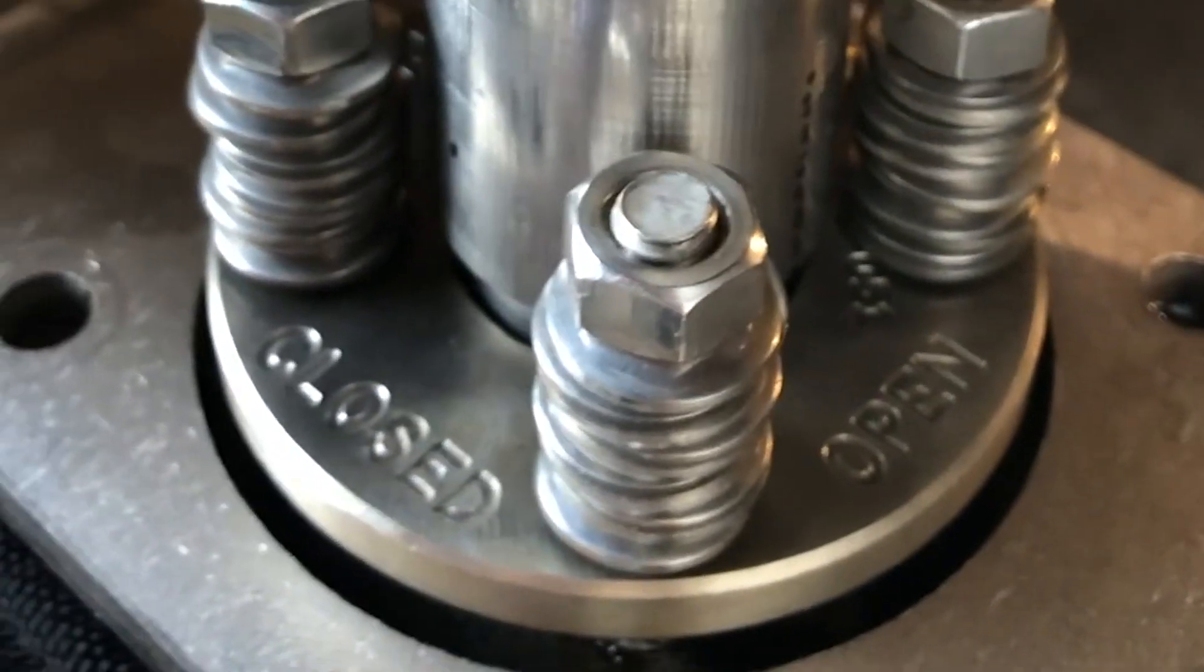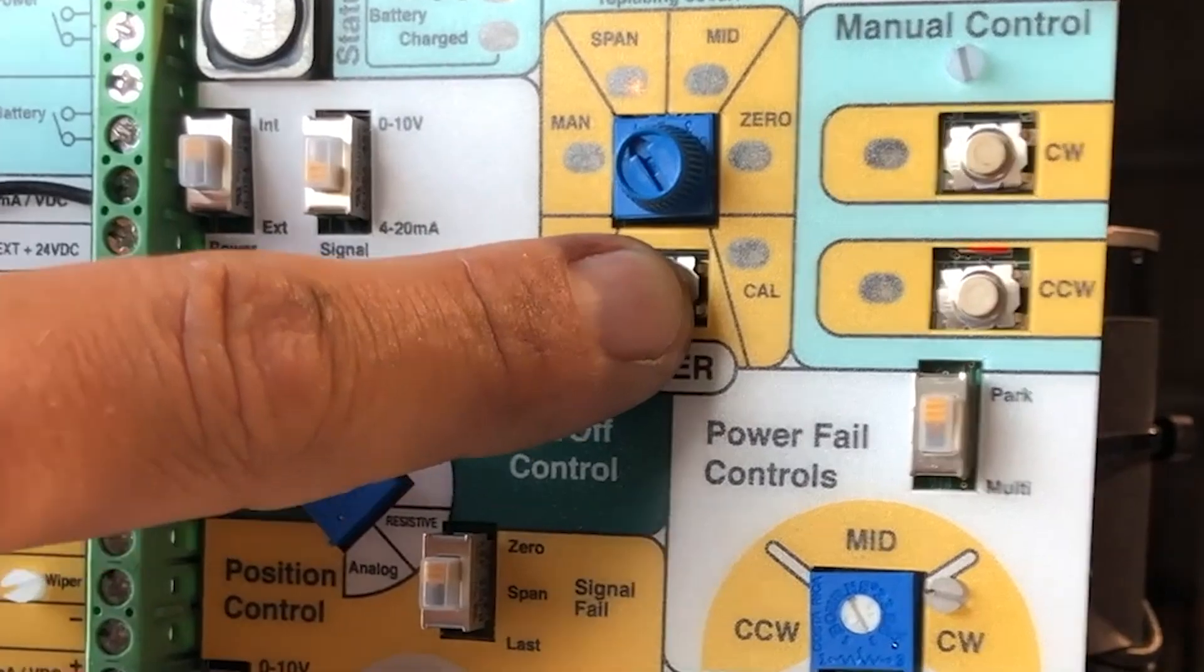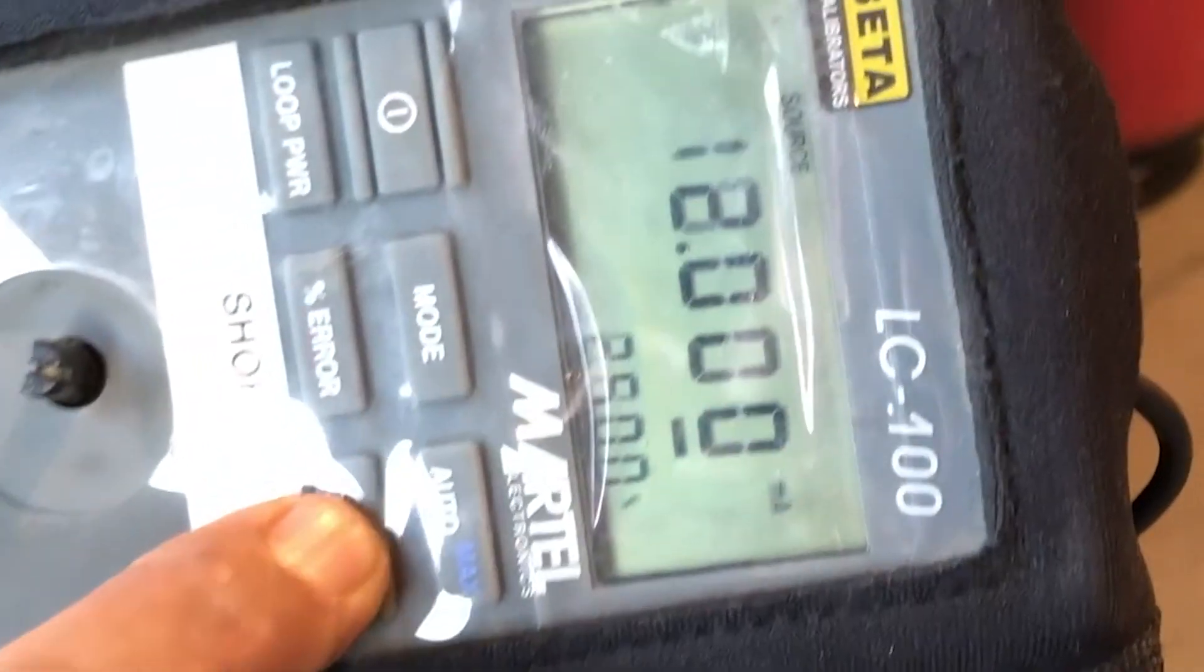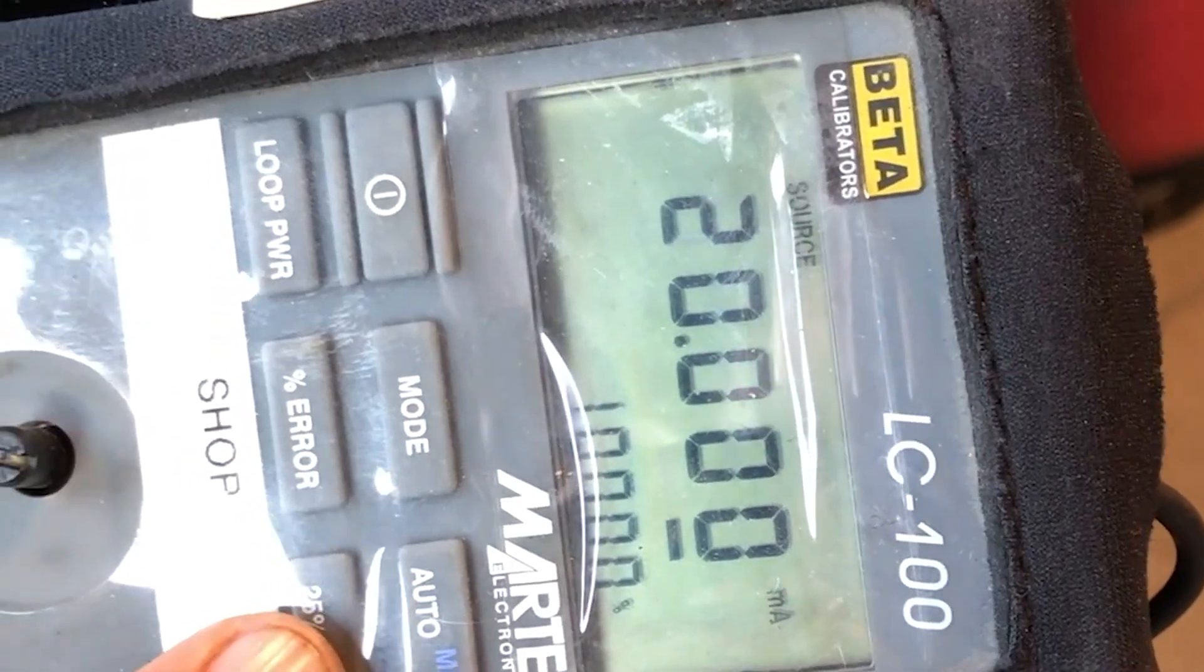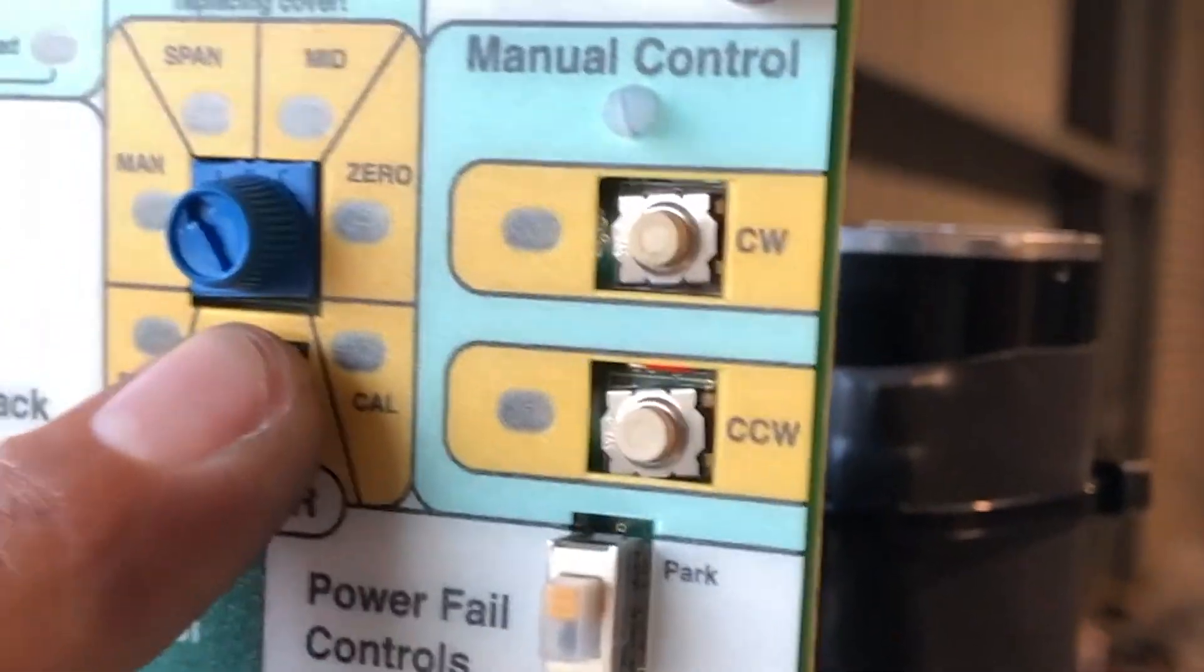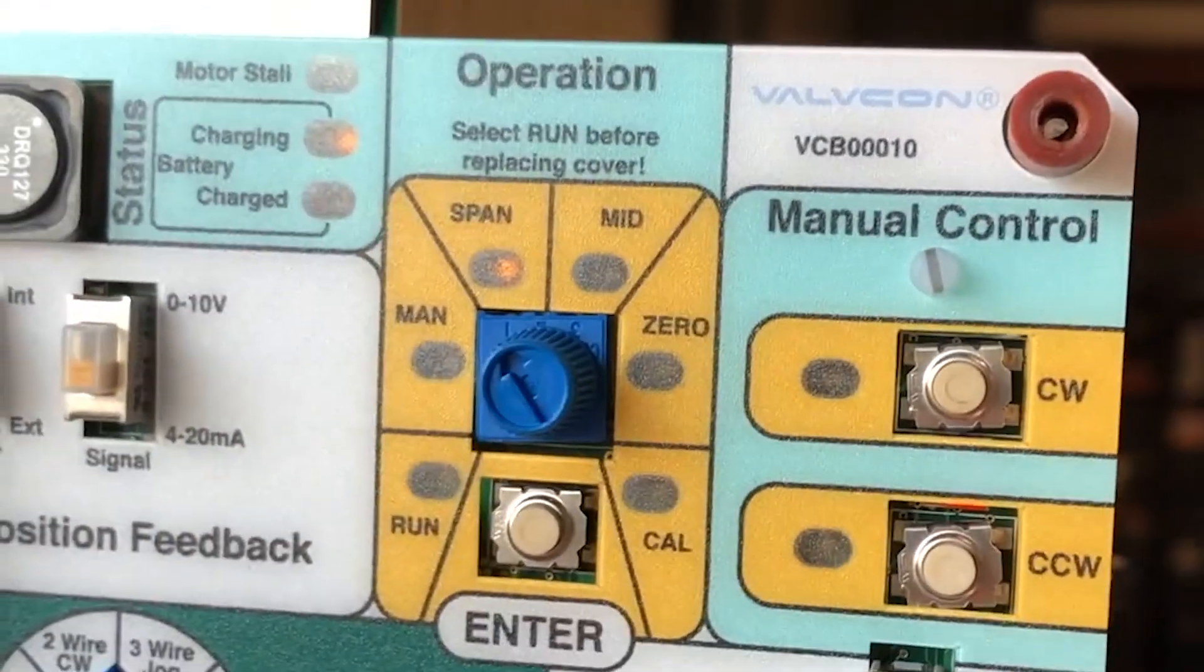Next we want to hold down enter for one second. We want to supply 20 milliamps to our actuator. We want to press enter for the actuator to take the change.